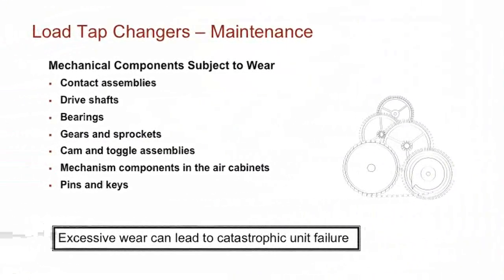The tanks, you also have tap changers that are in-tank tap changers or out-of-tank type tap changers. What you have to concern yourself with there is the gasketing material. You have doors on some of these tap changers. You've got gaskets, what we call the nitrile, I guess is what they are, behind the gasket doors. Typically you'll get about 30, 40 years of service out of those gaskets. But if you open up the door, you want to replace the gasket every single time.